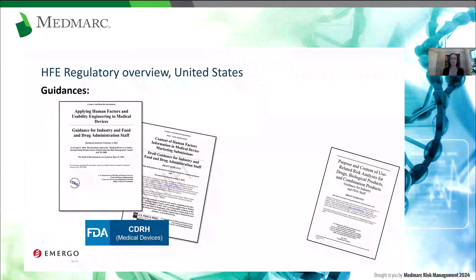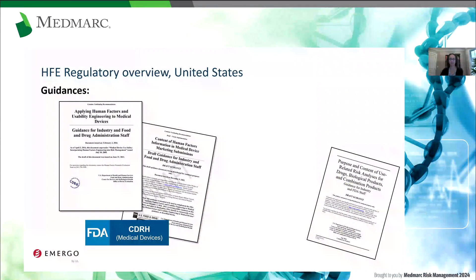Here I'll get started with the regulatory overview for the US. The most pertinent guidance document set forth by CDRH — the Center for Devices and Radiological Health, which regulates medical devices in the US — was published as a final guidance in February 2016. It still represents the FDA's current thinking on human factors. It's a very easy-to-use document — clear, only about 50 pages, with some nice examples. If you have any responsibility for human factors in your role, I highly recommend reviewing this document if you're not already familiar with it.